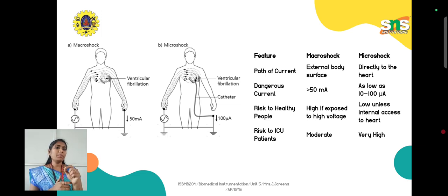The risk to healthy people is high for macroshock, and low for microshock unless there is internal access to the heart, because no one will go directly with an invasive method. So the chance of getting a macroshock is high compared to microshock. But if the person is undergoing an invasive procedure, then microshock has a high risk compared to macroshock. It depends on whether the person is going through a non-invasive or invasive method, using an internal or external device.